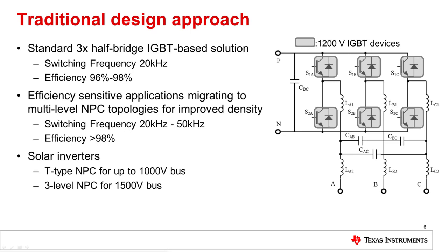Multi-level topologies reduce the switched voltage to enable higher switching frequencies and smaller magnetics. For example, the typical topology seen in the solar string inverter industry today is the T-type NPC converter for buses up to 1,000 volts and three-level NPC converters for buses up to 1,500 volts.